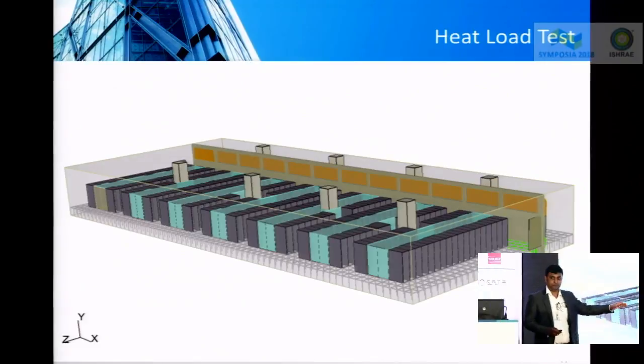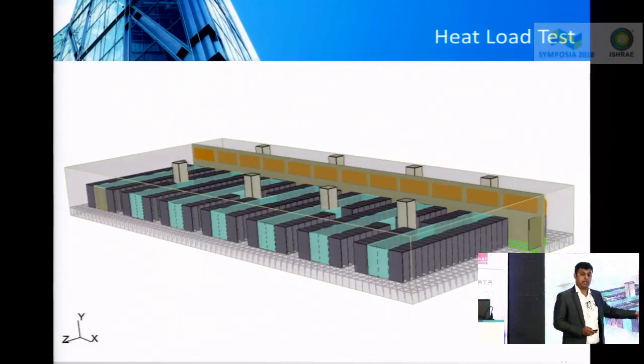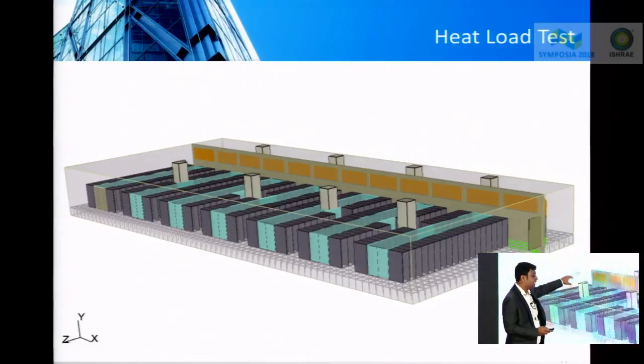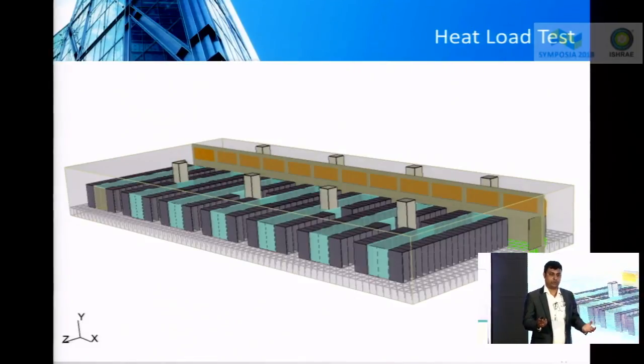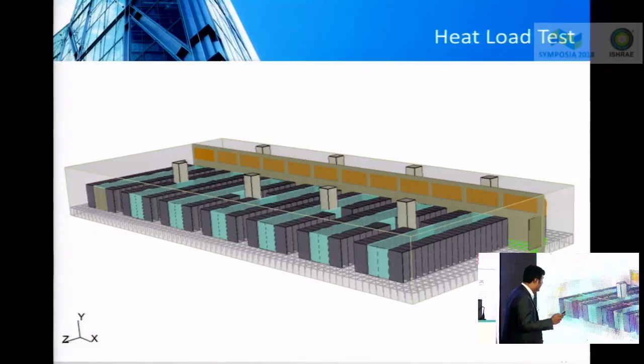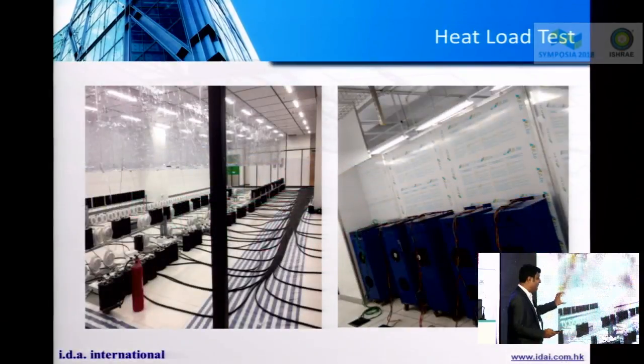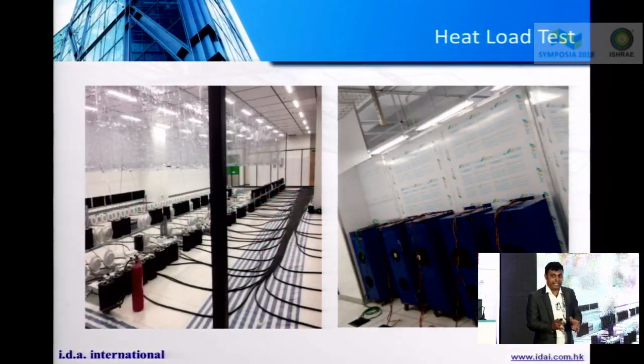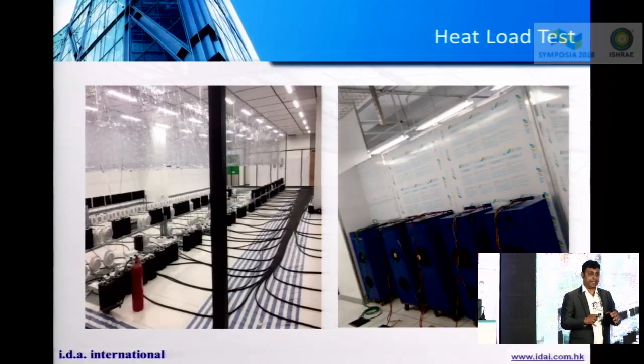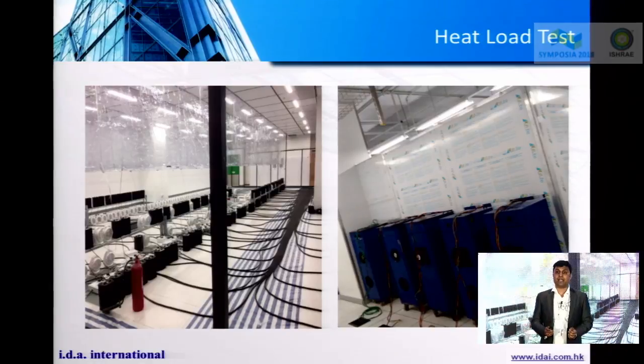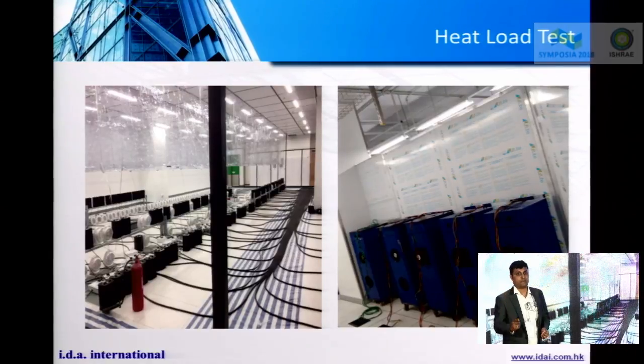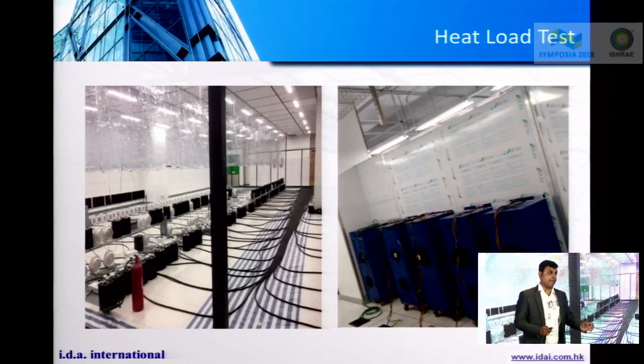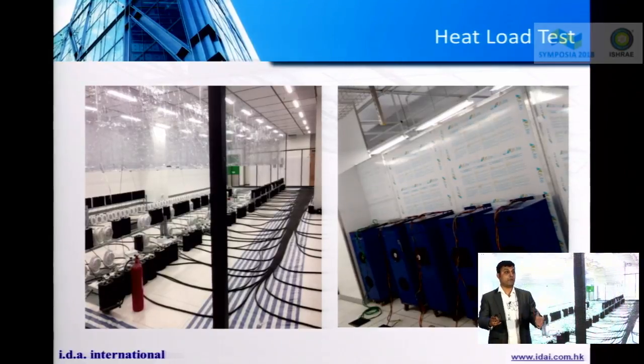Let's assume we have a data hall with multiple racks, with cold aisle containment, and the CRAC units at the periphery, which is how you traditionally design a data center. Now, the way I will start my heat load test is, the first thing I have to do is place heat banks. Now, each of these heat banks will represent one single rack. So if my data hall is designed for 10 kilowatts per rack, I would have one heater of 10 kilowatts placed at the location of the rack. So if my data hall is designed for 1.5 megawatts or 2 megawatts, I will place the same number of heaters that can generate 1.5 to 2 megawatts.